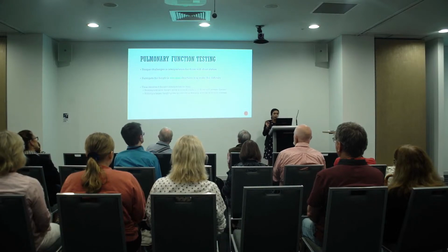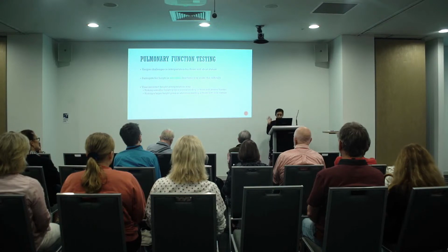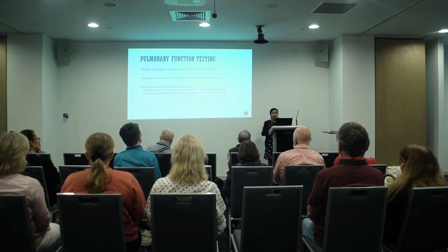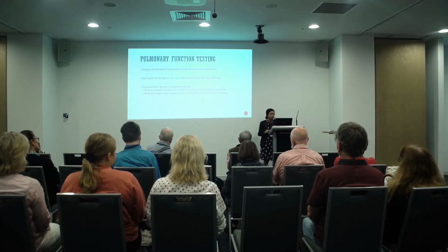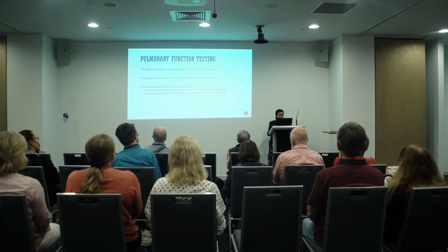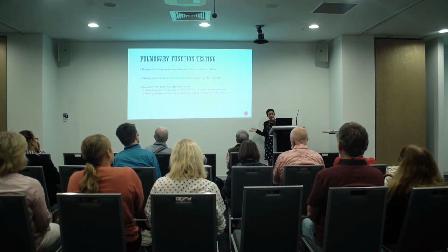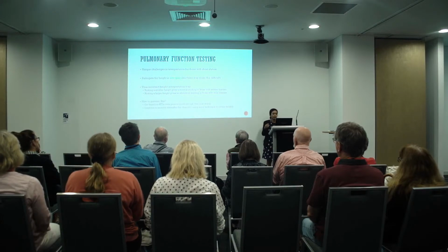Now, if you pick the incorrect height, so if you pick a smaller height because you've decided to measure someone from the end of their wheelchair to the head, which is not correct, but I've seen people do it, you might get a normal lung function reading when you actually have quite severe disease, because they're comparing you to someone of that height, which might be a 120 or 100 centimeter person. And again, if they just estimate your height, so they pick a larger height than you actually are, you might get an abnormal lung function reading and have to go through all these other tests when you've only got mild disease. So what do we do to try and overcome this?